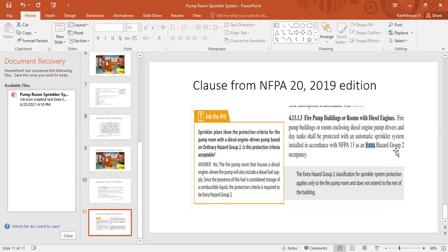But in my experience I have typically seen in many projects, many people have considered that as an ordinary hazard. What they did in sprinkler system designing, they made with 12.1 square meter spacing as an ordinary hazard spacing. This is completely wrong. Many people have made this mistake in classification of hazard on fire pump room.